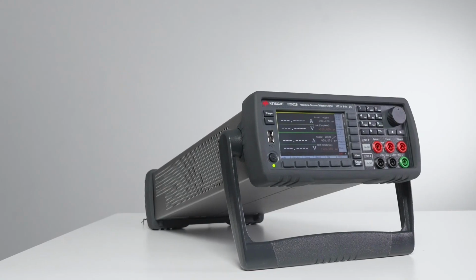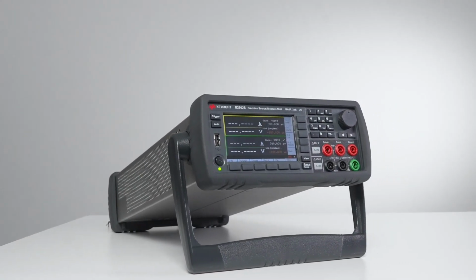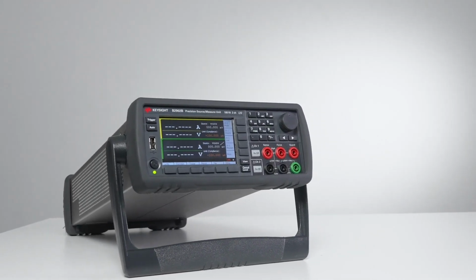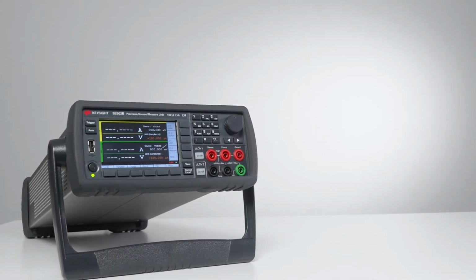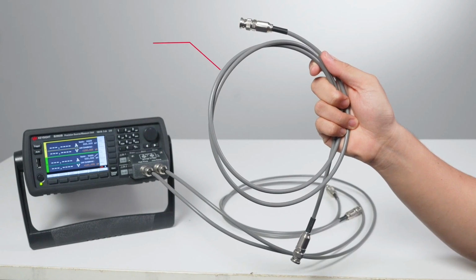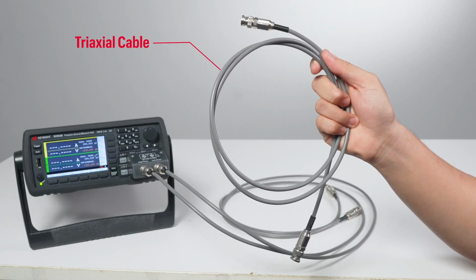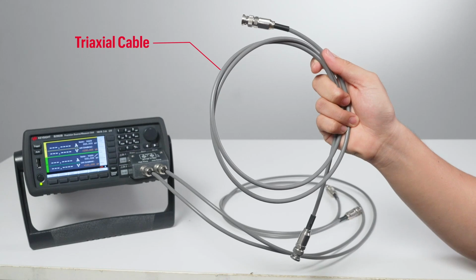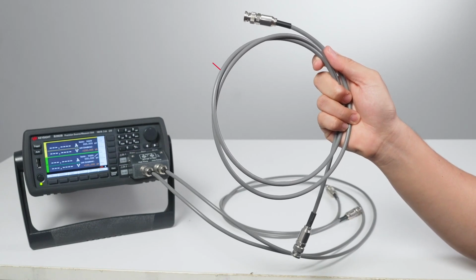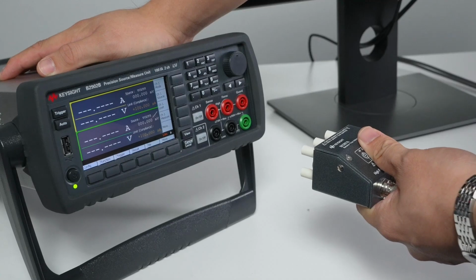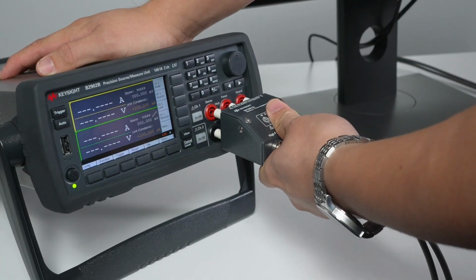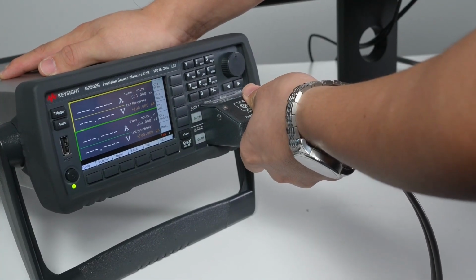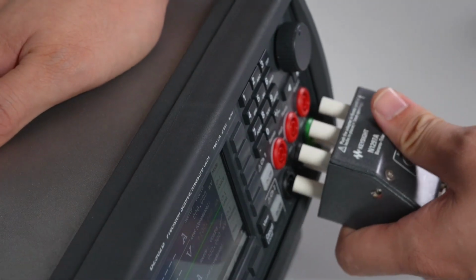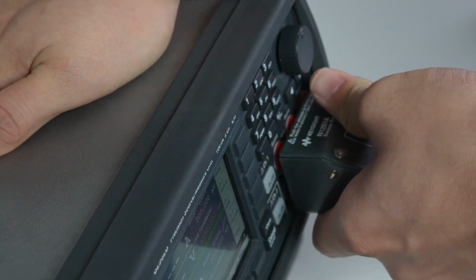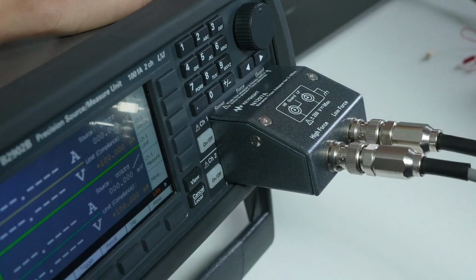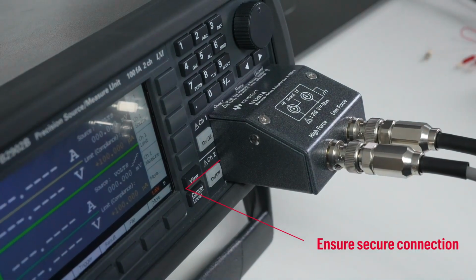The FET transistor is placed inside the N1295A test fixture box that shields the FET transistor from external noise. To achieve precise low current measurements with femtoampere resolution, we utilize a triaxial cable to establish a connection between the device under test and the B2900 series. The terminals on the B2900B are banana jack, so use this N1297A adapter to convert the banana jack to a triaxial terminal and connect it to the triaxial cables. Please firmly insert them all the way in.